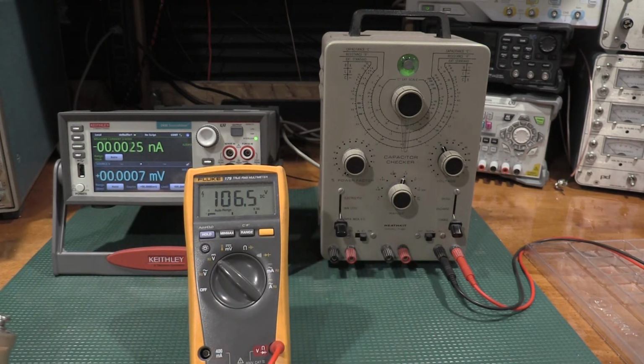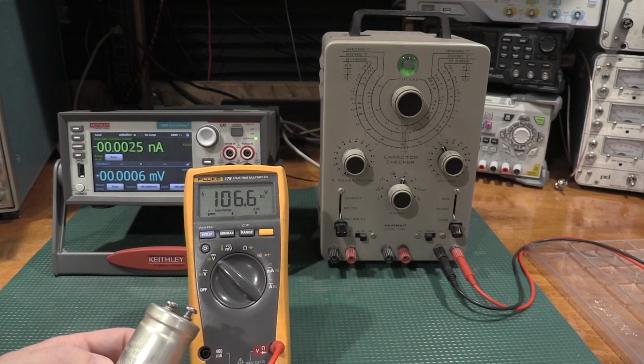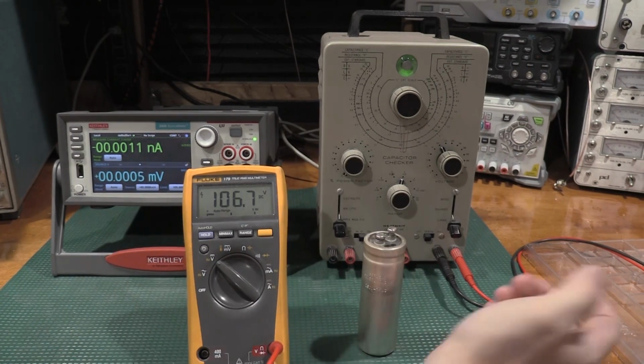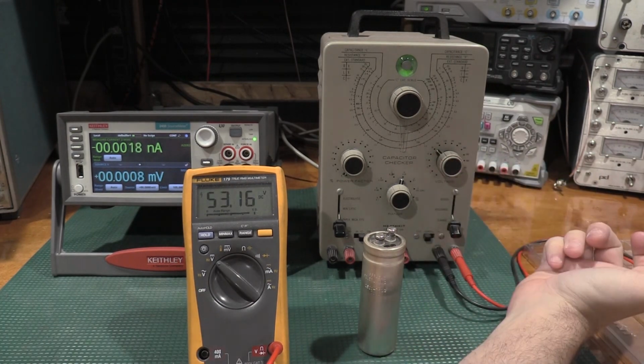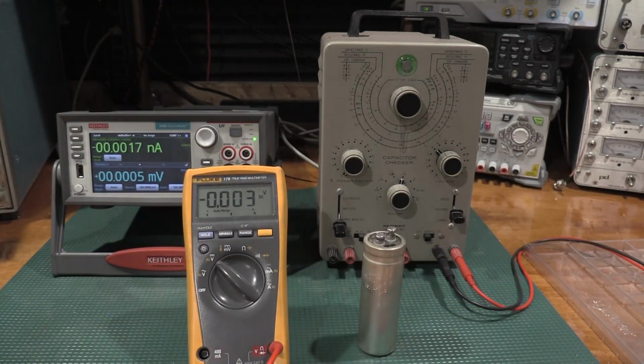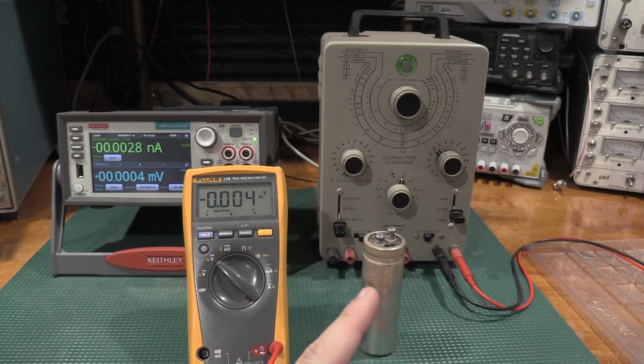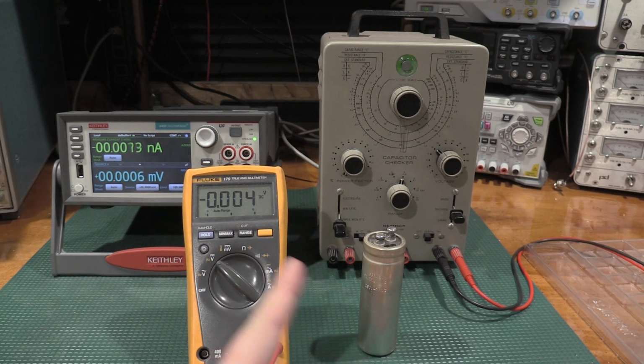So let's see. This is a 2500 microfarad at 75 volts DC. So if I set it to 50, we're at 53 volts. That'll be safe for the cap. So we'll turn this off the discharge so we don't get shocked. And then I'm going to hook the capacitor up to the tester, and then I'm going to hook the meter up to the capacitor, and we can see what's going on.